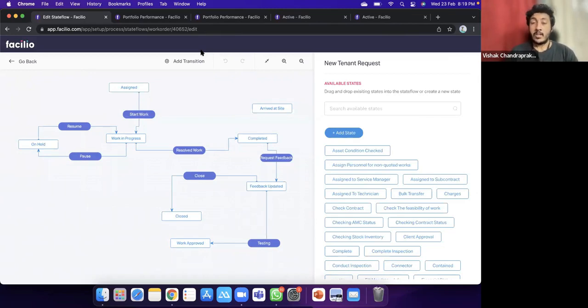So if there's an issue, let's say an overcooling issue within a certain space, we can identify that it's because a cooling coil valve malfunctioned within the VAV unit serving that space, because we can identify the relationships between these different systems. That's then tagged as the root cause, and a work order is created and assigned.